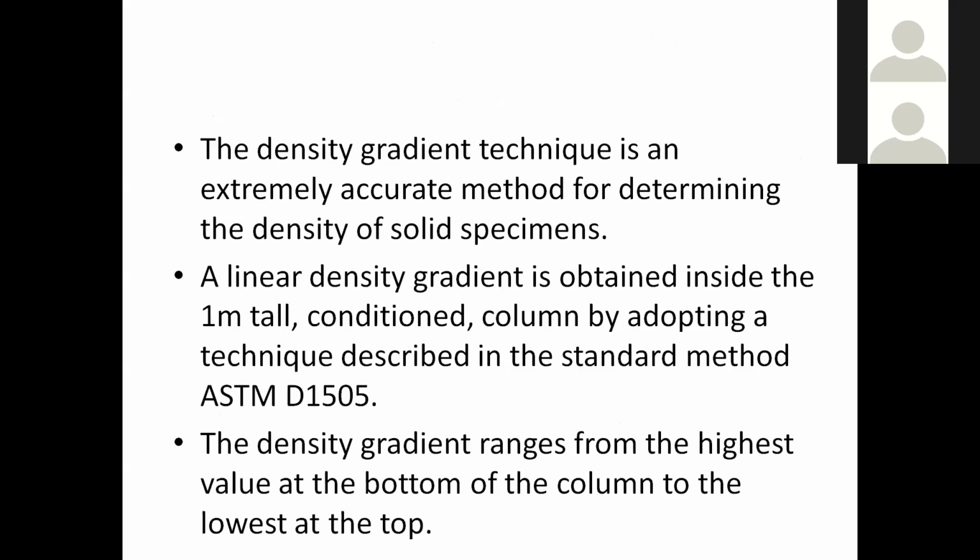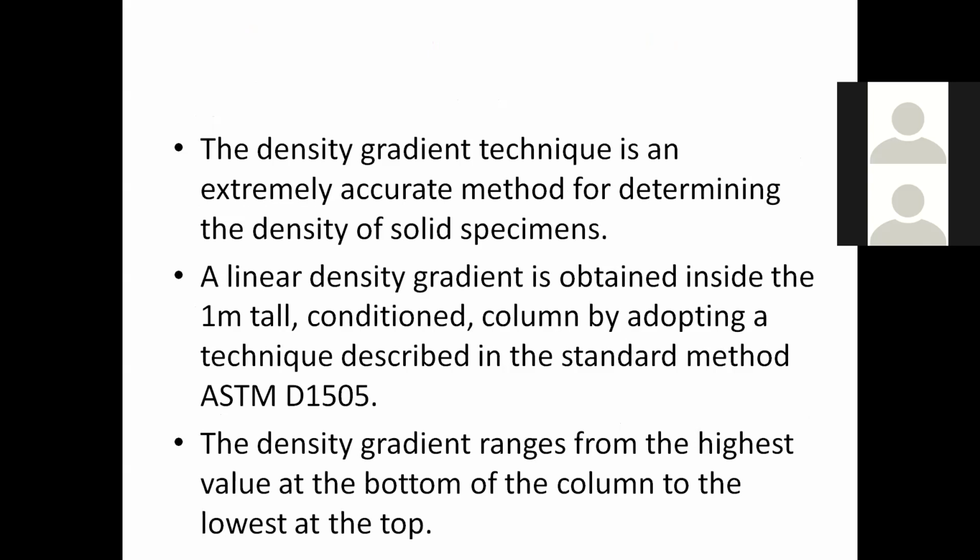The density gradient technique is an extremely accurate method for determining the density of solid specimens. A linear density gradient is obtained inside the 1 meter tall conditioned column by adopting a technique described in the standard method ASTM D1505. This is the American standard for testing of materials, for textile materials. D1505 is referred to when we measure the density of fibers and other solid specimens by using a density gradient column.